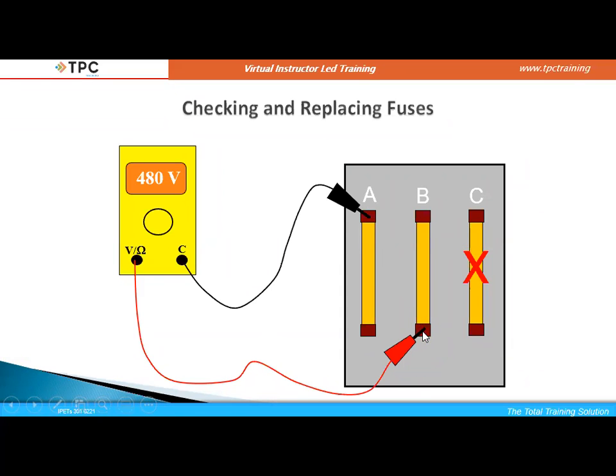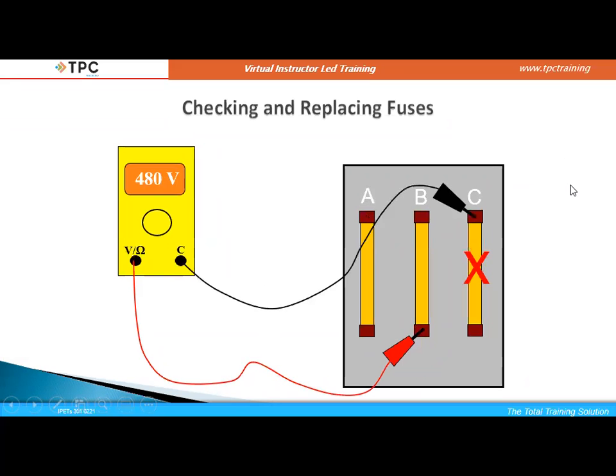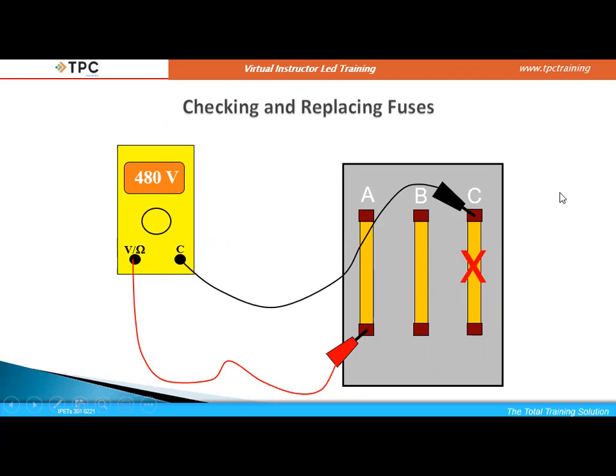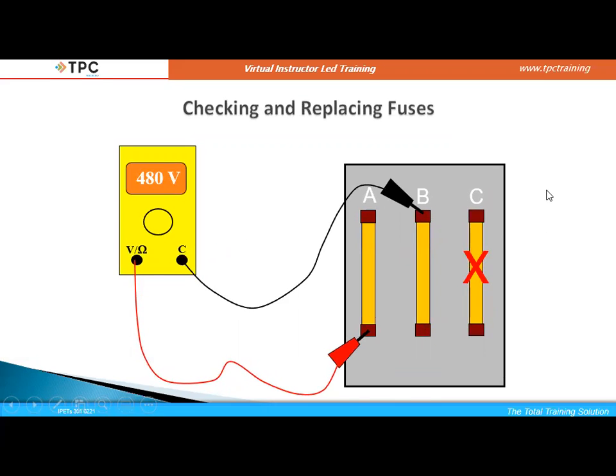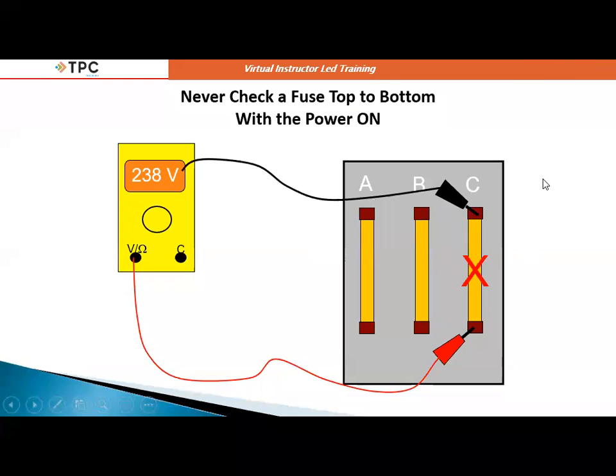If I continue with the crisscross method, notice I'm still on the line side of A. I could go on the load side of B or C. When I go to B, I see the meter does say 480. So phase B is a good fuse. I come to C, I know that phase B is still a good fuse. I go to the load side of phase A, that is a good fuse. So the only fuse I found bad here was phase C, and phase A is still good. Continuing with the crisscross method, this is what OSHA does not want us to do. They do not want us to check a fuse while the equipment is energized when we go from the top of the fuse to the bottom of the fuse with our meter.